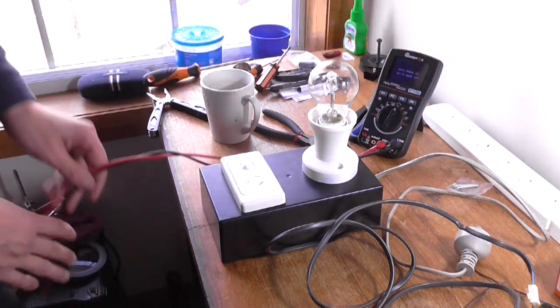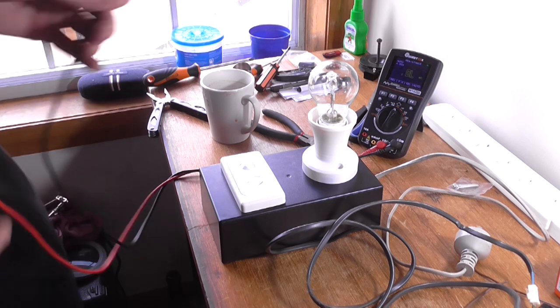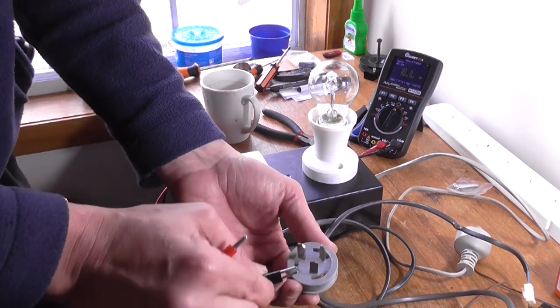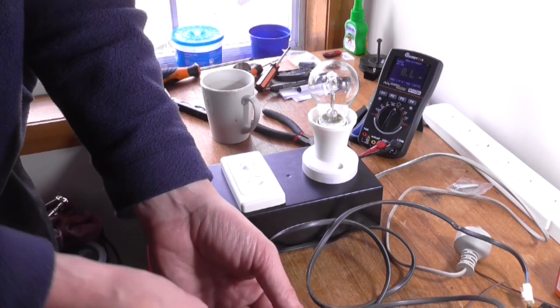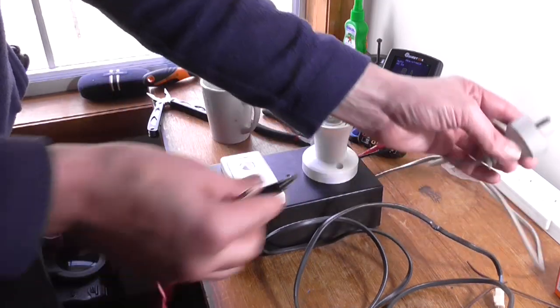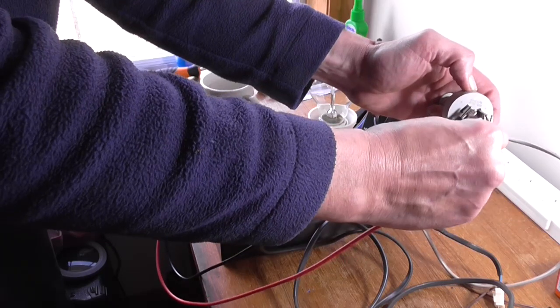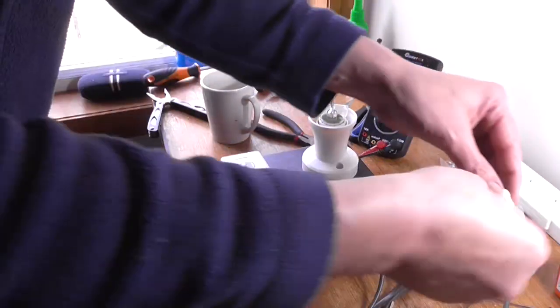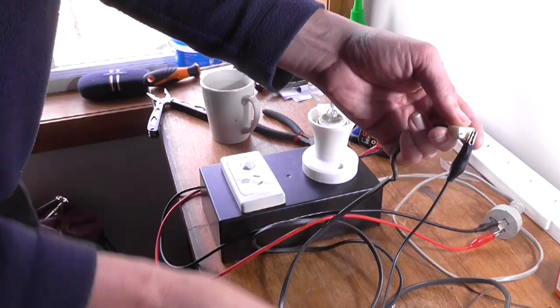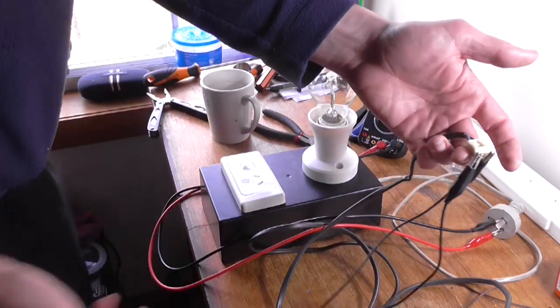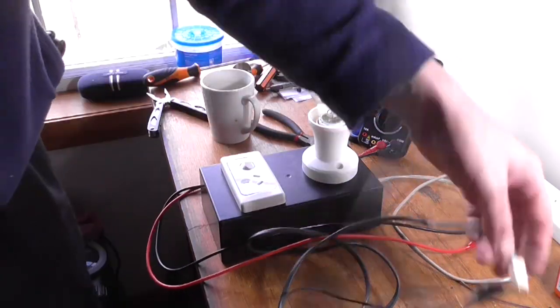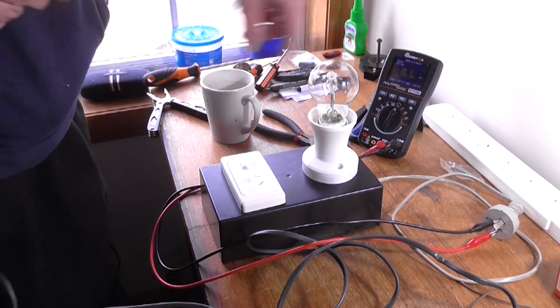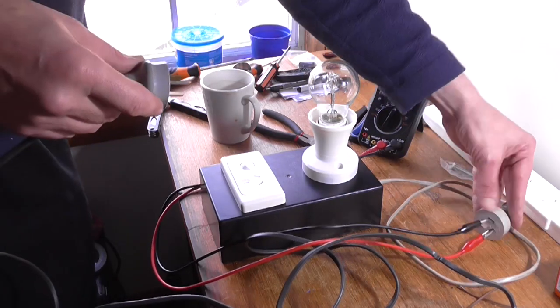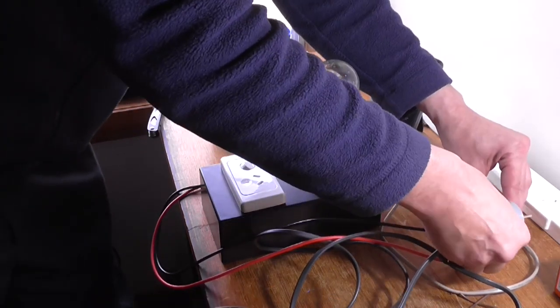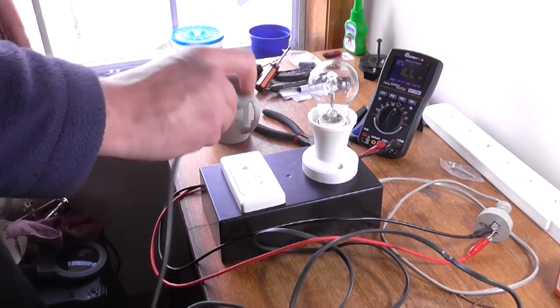Now you may be wondering why it was important for us to know what the actual DC resistance of that light globe was. Wrong one. Because we want to test this in the worst case scenario where we have a line cord, which I've got in my hand here, where both the active and the neutral are shorted together. Now that's counterintuitive, but if we measure the resistance across what comes in from the wall, if the lead will stay on there, we plug this into our tester.